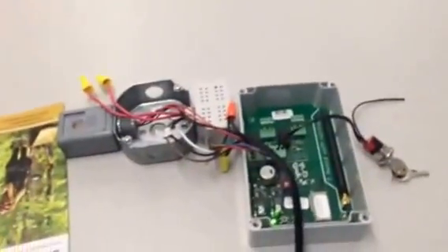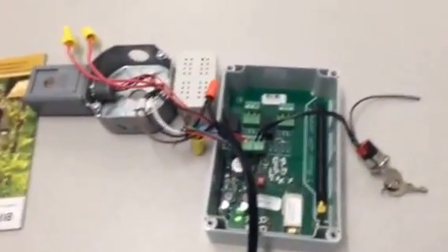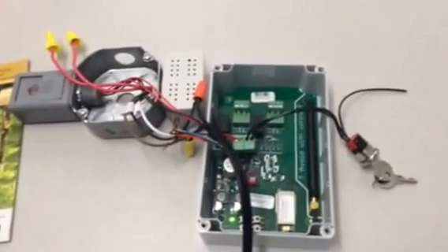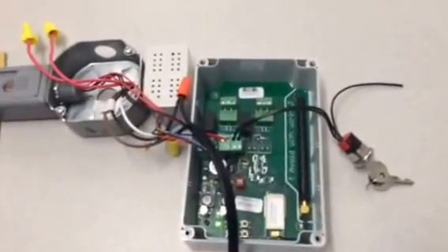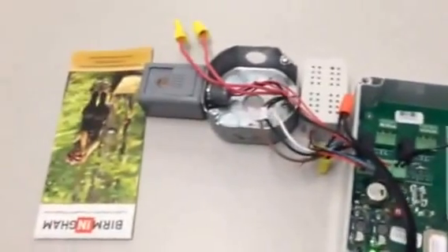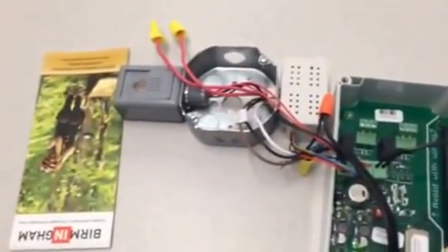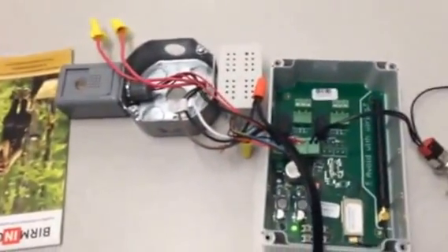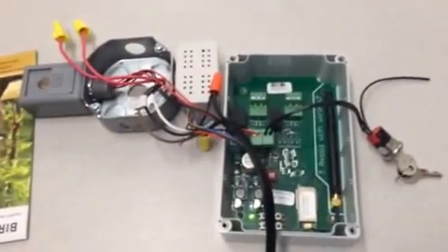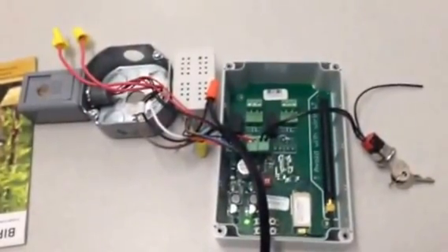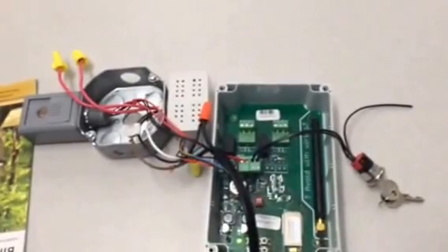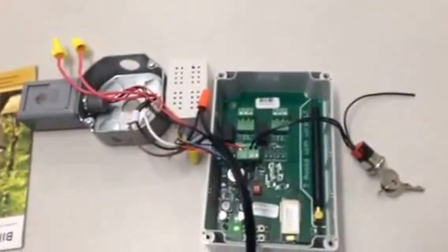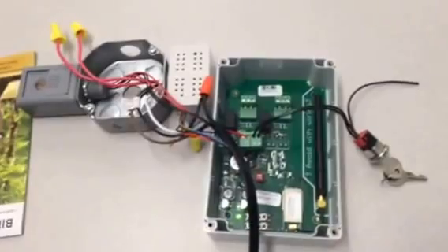The last piece we'd like to show is a wireless input. This is running on the 802.15 IP-based RF network, and this controller is universal inputs, universal outputs, and what we're showing here is two digital inputs, a photocell and a switch, where we can see this being used maybe for monitoring of submeters, using pulse meters, taking it in as an input, and not having to run a wire or a data line or an IP connection down to every meter point.